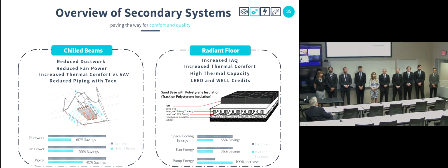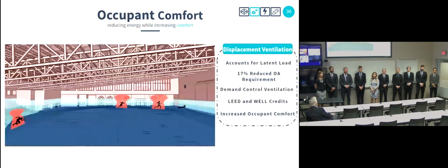There is an increase in our overall pump energy due to this hydronic system, but it allows us to save mechanical energy overall. Displacement ventilation will be paired with the radiant flooring in the track and field and practice field location. This accounts for the latent load. By utilizing displacement ventilation, we're allowed to decrease our outdoor air requirement by 17%. However, we are supplying 10% more than what is necessary to increase occupancy comfort in the space. This will be paired with demand control ventilation, utilizing CO2 sensors in the space.